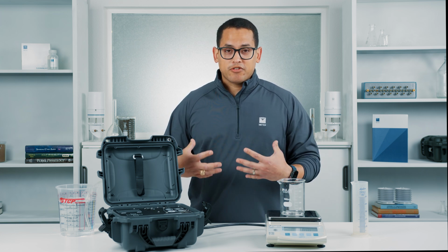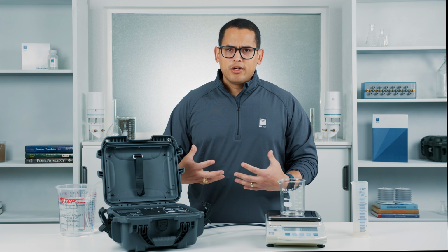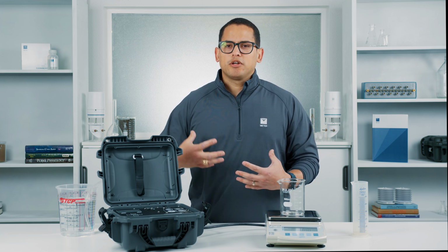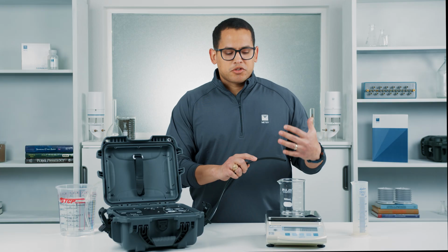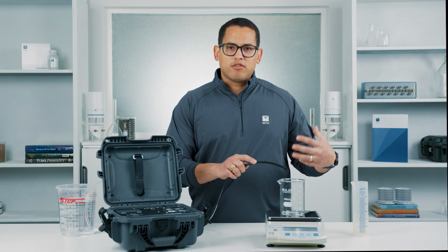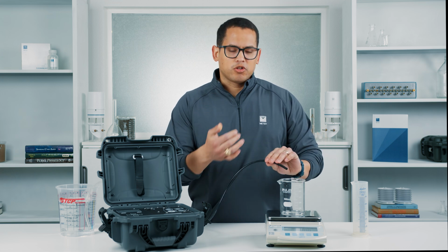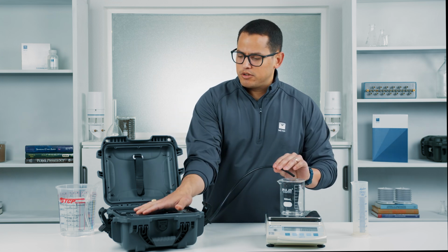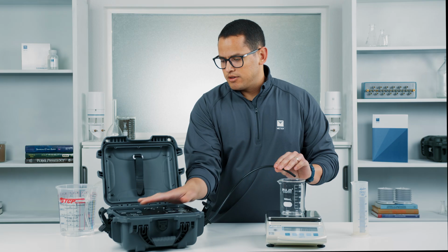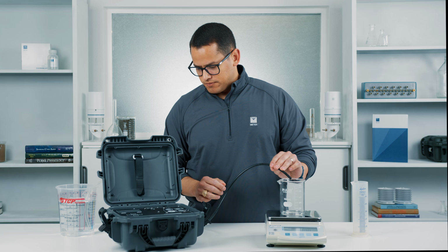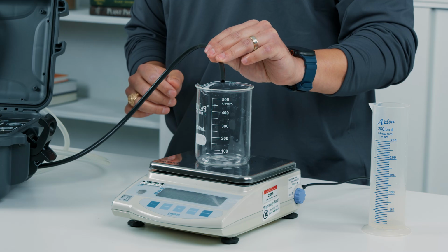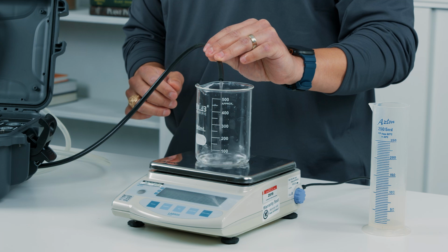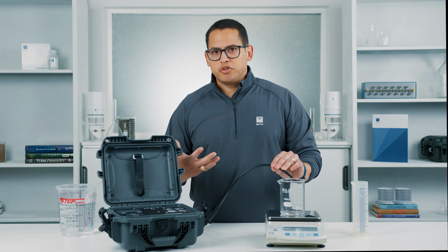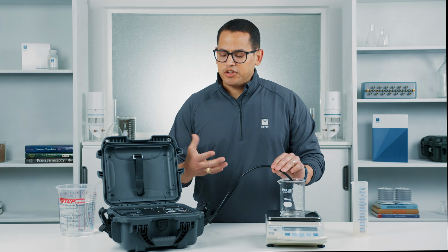To get that calibration process started, again, the first thing it's going to do is try and purge the line of any air. So we're going to run through that purge process to make sure we clear out the lines of any air, so we're only pumping water during the calibration routine. At the screen, again, it's going to ask you to check to make sure everything's connected and that you have a water source feeding into the device, and you have your line feeding to the reservoir that's going to be capturing the water. It typically takes 2 to 3 routines of the purge to get a nice clean line, so we're going to do that again.